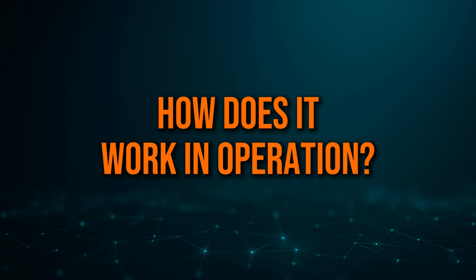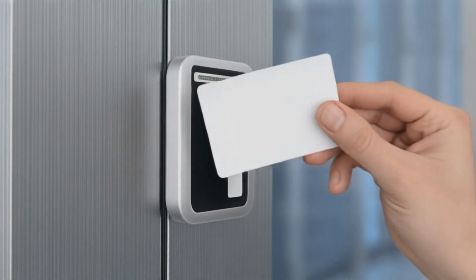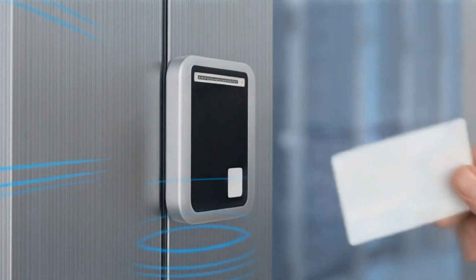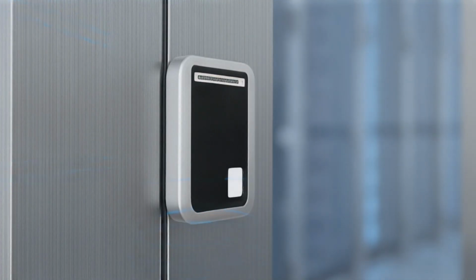So now that we've covered the setup, let's see how this actually works in operation. When an engineer badges into a server room, the PET7060 detects the signal and instantly communicates with the control center. If the credential is valid, the control center sends the unlock command. If it's not, the door remains locked and the system automatically records the attempt and generates an alert. It's precise, automatic, and fully auditable. No guesswork and no paper logs.